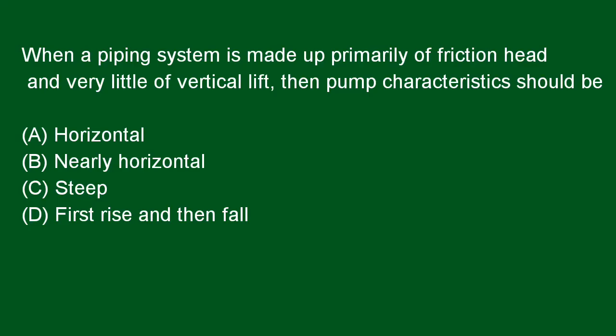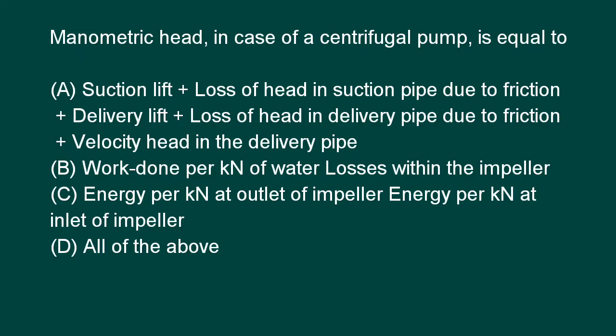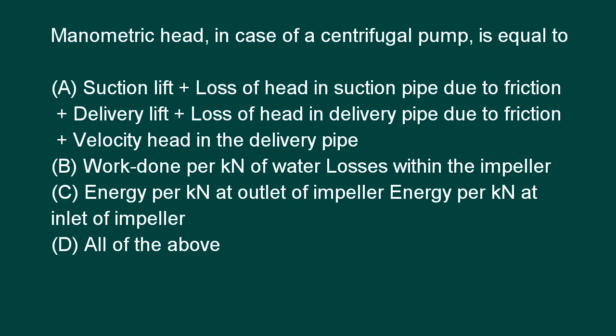Next question: When a piping system is made up primarily of friction head and very little vertical lift, then pump characteristics should be nearly horizontal. Answer B is right. Manometric head in the case of a centrifugal pump is equal to: suction lift plus loss of head in suction pipe due to friction, plus delivery lift, plus loss of head in delivery pipe due to friction, plus velocity head in the delivery pipe. Option D — all of these — is right.